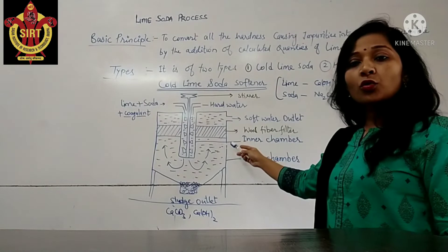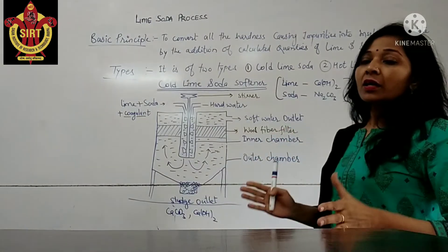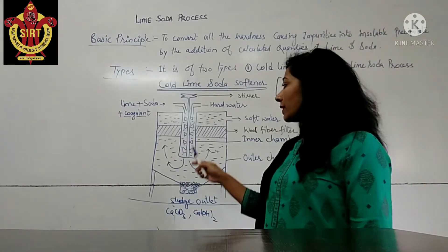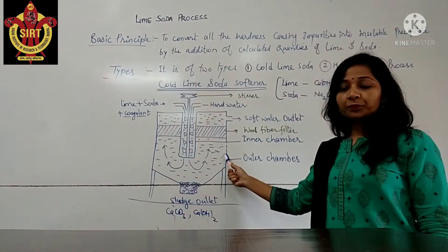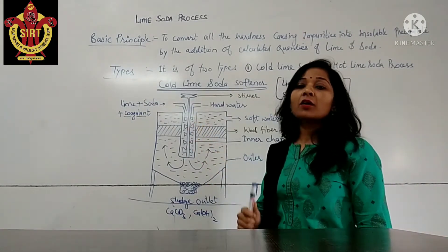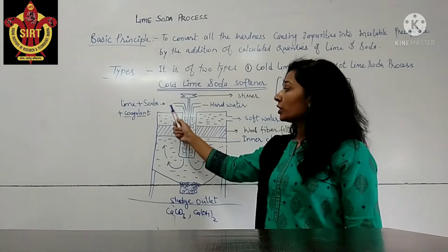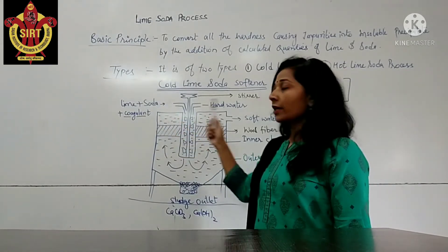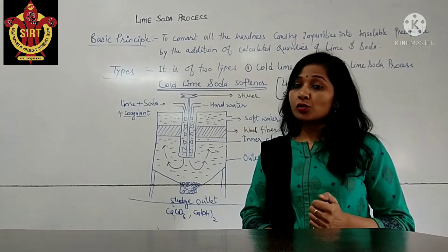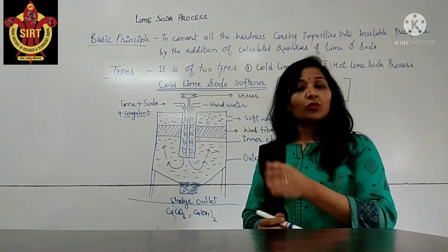Here is the diagram for the cold lime soda softener. Cold lime soda softener is a cylindrical-shaped instrument having two chambers — one is inner chamber and the other is outer chamber. The inner chamber has a mechanically operated or motor-operated stirrer. It also has two inlet valves: one inlet for the addition of lime soda and coagulant, and the other inlet for the addition of hard water. A coagulant is also used here.